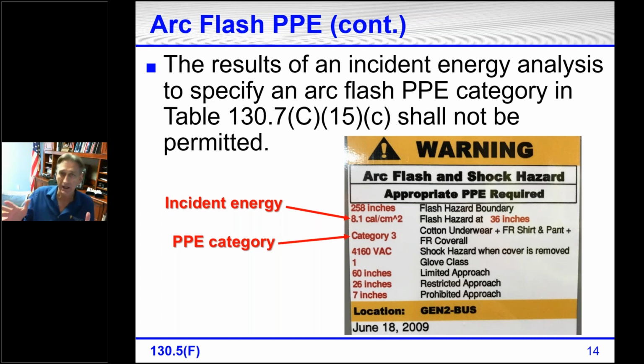This was a draw out type circuit breaker, a rack in, rack out type circuit breaker. So typically the working distance is anywhere from 24 to 36 inches or so. This shows 8.1 calories. Well, a category 2 has to be at least 8 calories, so anything over that would jump to a category of 3.